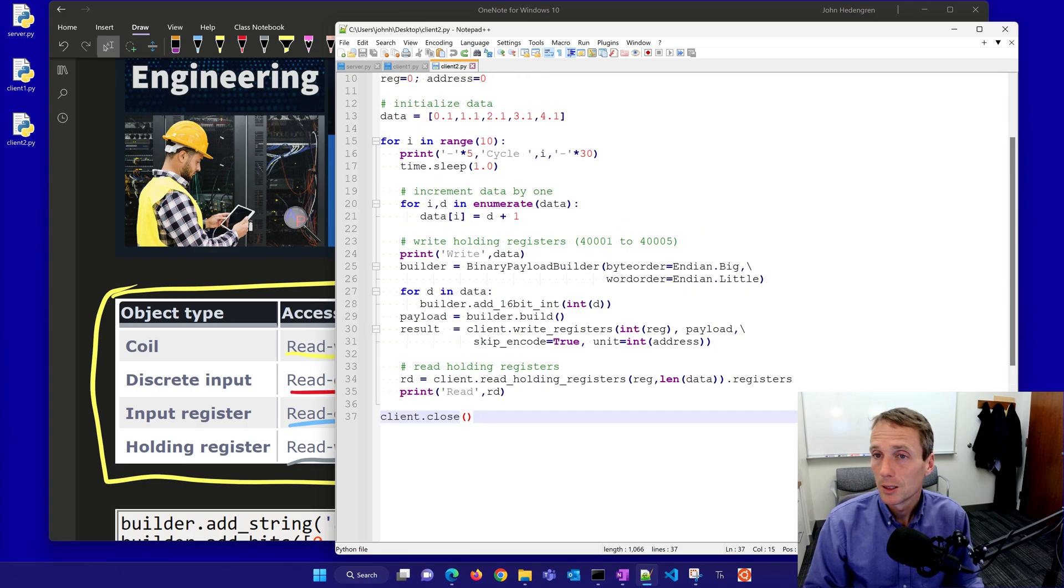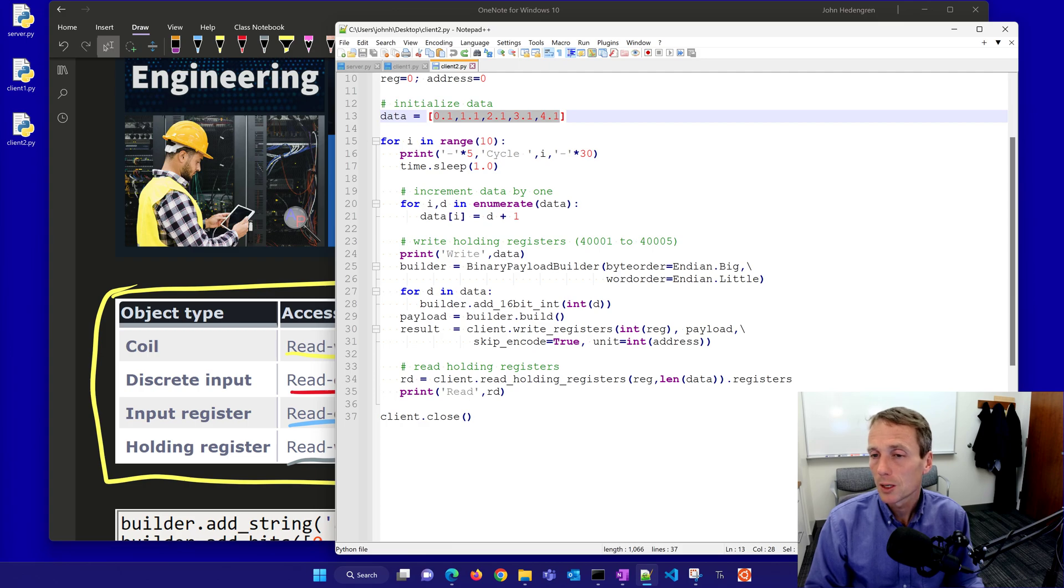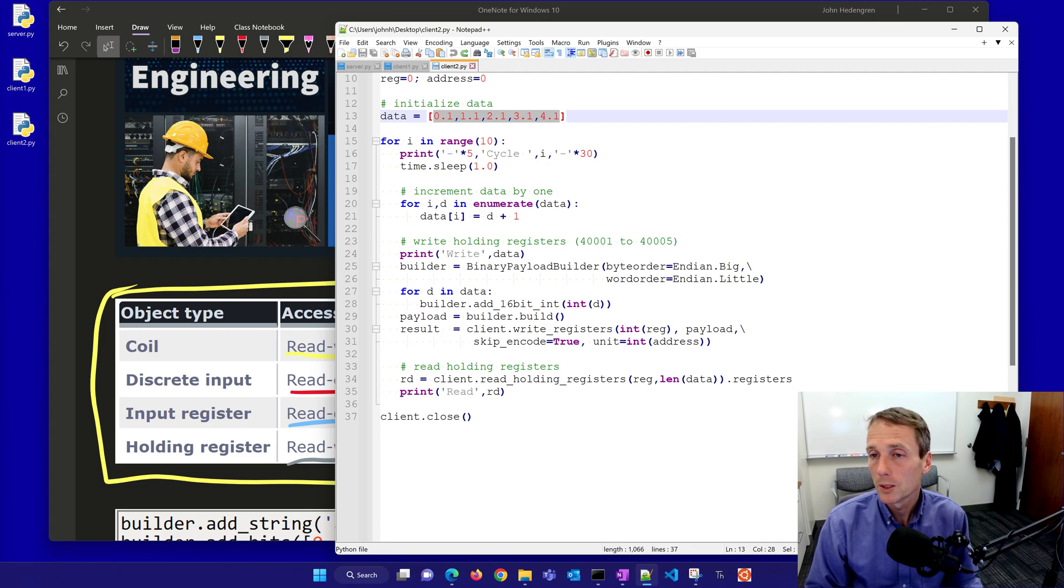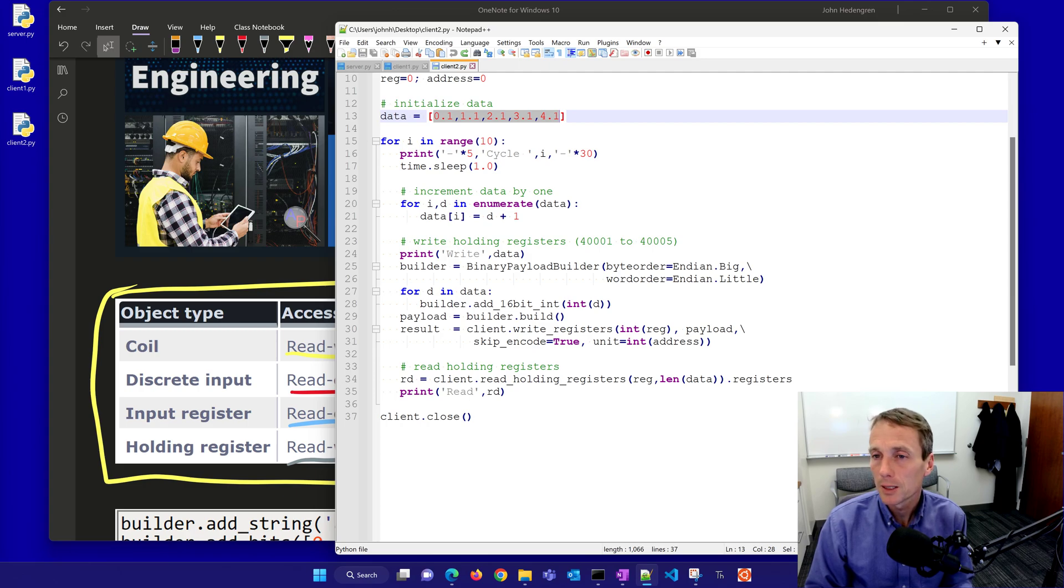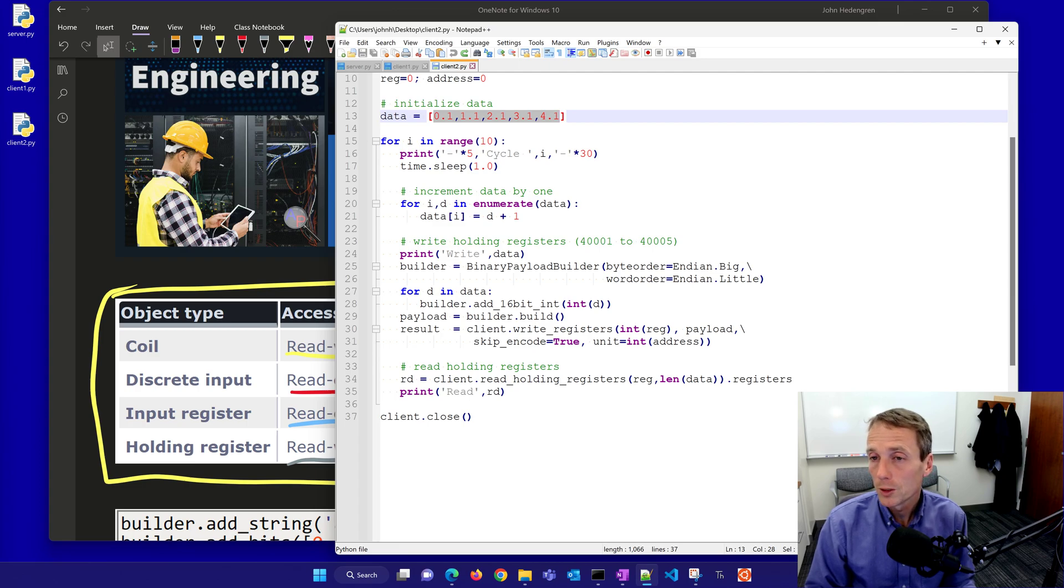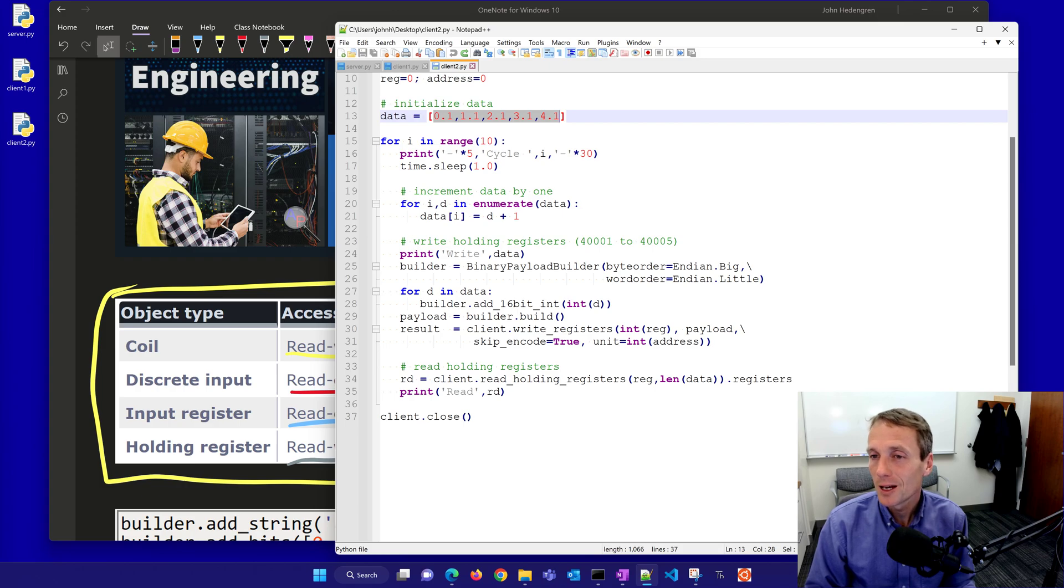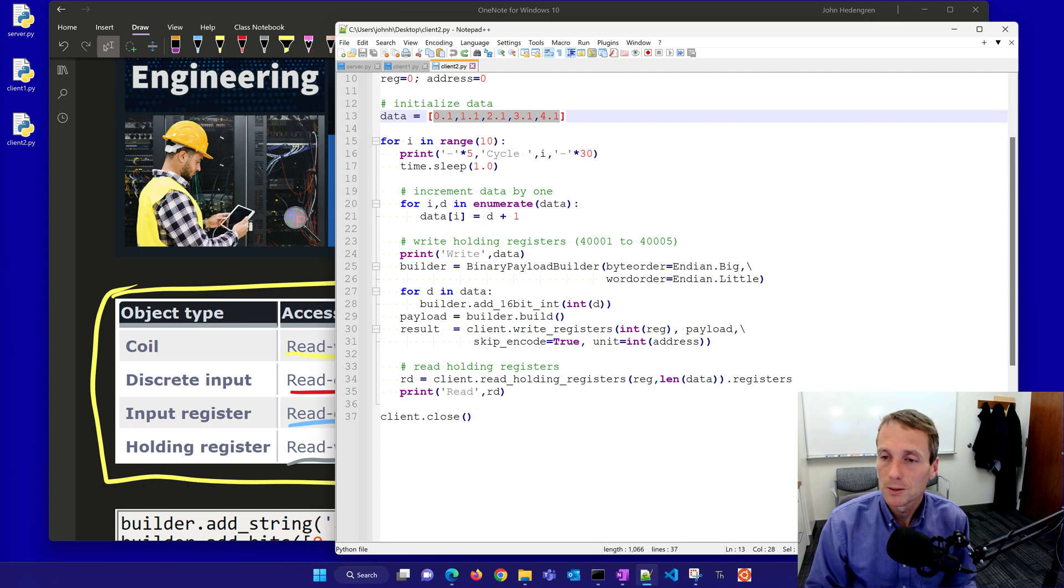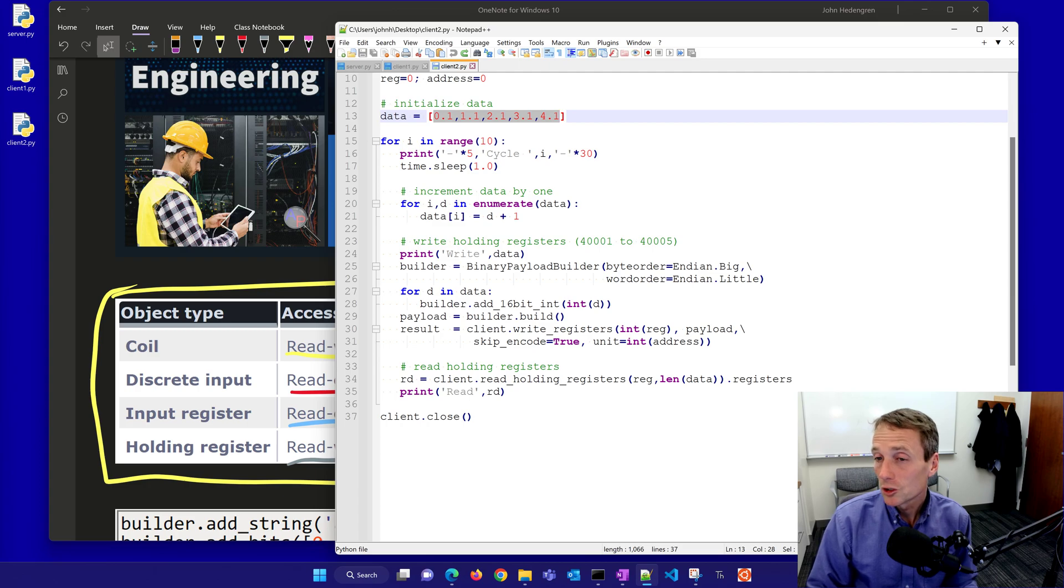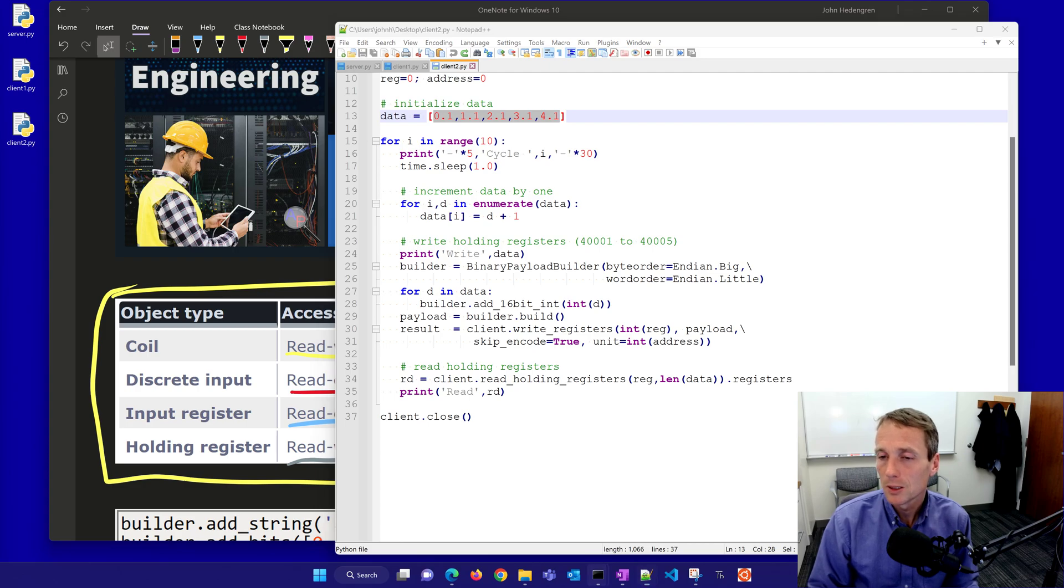One thing you'll notice is that these all have decimal places. There's a couple tricks that people in the industry use with this standard 16-bit holding register. You can put two of those together to make a 32-bit number or four of them together to make a 64-bit number. A 32-bit number is going to give you about seven decimal places of precision. A 64-bit number about 14 decimal places. This 16-bit integer had to be integer values between a certain range up to like 32,000 to negative 32,000. It depends on what you're trying to store. You've got to pay attention to the values that you're going to be storing.